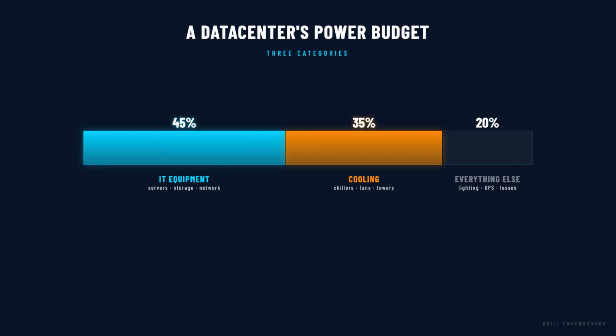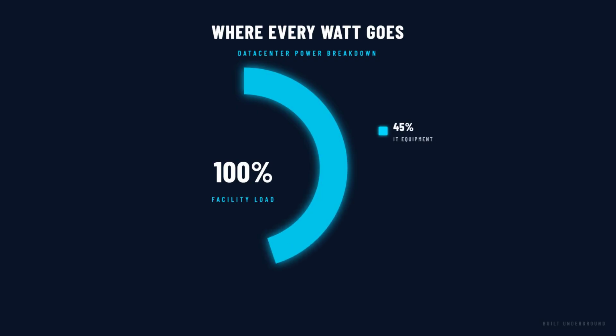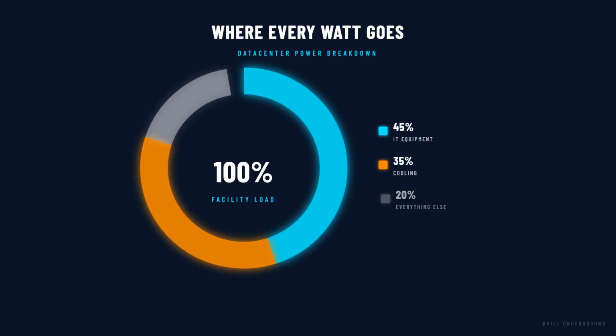Cooling systems, the chillers, fans, pumps, and cooling towers that remove all the heat generated by that equipment, consume another 30 to 40%. Everything else, lighting, security systems, UPS losses, power distribution losses, and on-site offices, takes the remaining 10 to 20%. The ratio between total facility power and the power actually reaching the IT equipment is called PUE, power usage effectiveness.